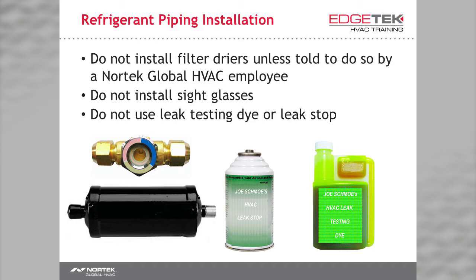Next is filter dryers. Unless you were told to install a filter dryer, by me, do not install a filter dryer. With the compressor protections built in and the fact that a broken winding or short will stop the compressor immediately, you are not going to have compressor burnouts. If there are contaminants in the system, they come from installation. We do have a process for adding them if needed, but again, contact Mr. McIntyre at Nortek before adding one. Next, we have dyes and leak stop. Do not put these in a system, period.